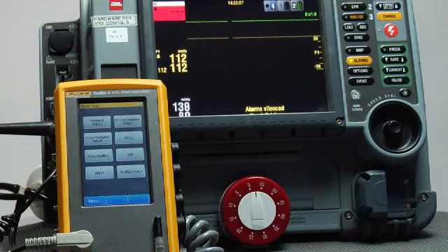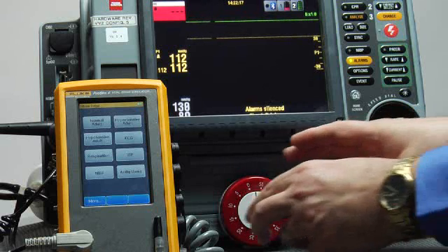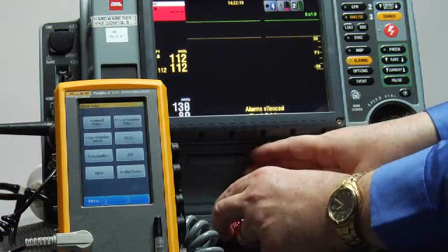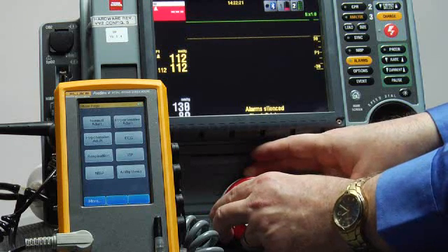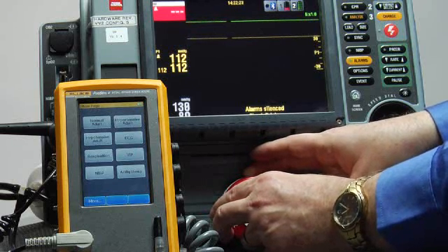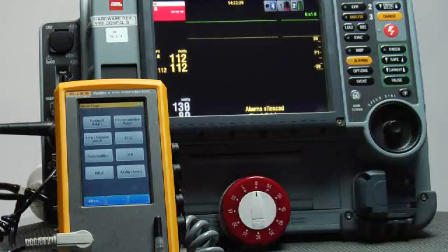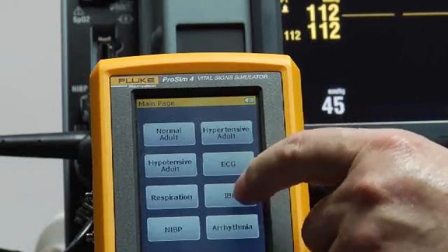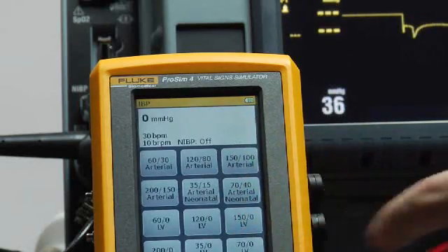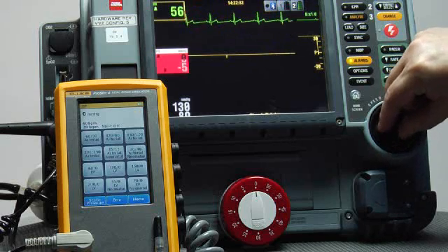We've come up to the unit, we've connected our ProSim 4 in place of the patient. So ECG is connected, NIBP, an invasive blood pressure line, and we're ready to start. Because we think we can do this in 60 seconds, I'm going to set the countdown timer to 60 seconds and we'll begin now. I will choose IBP and zero.